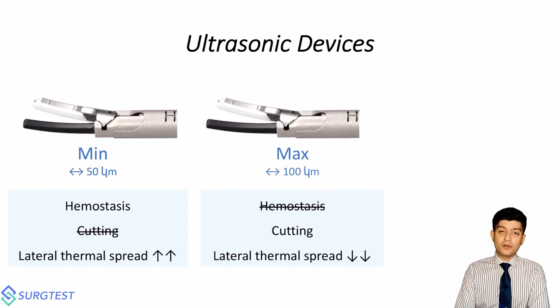In contrast, when you have a maximum excursion of the active blade, which is usually around 100 microns, you get less hemostasis, but the tissues get vaporized and get cut very, very effectively. On the flip side, the amount of lateral thermal injury is much lower. So collateral damage is less when you're using the maximum mode, but tissues are more likely to bleed because it does not produce effective hemostasis.